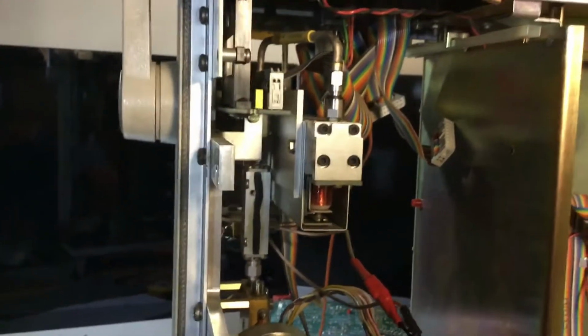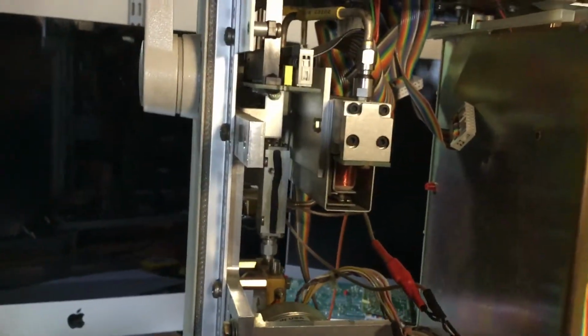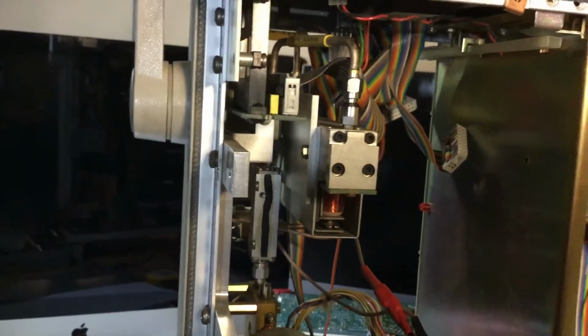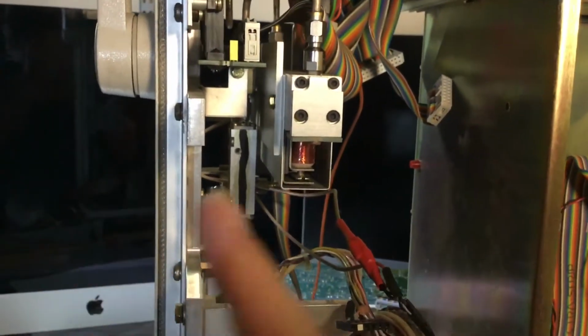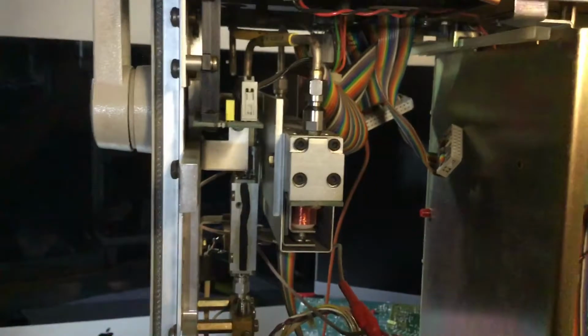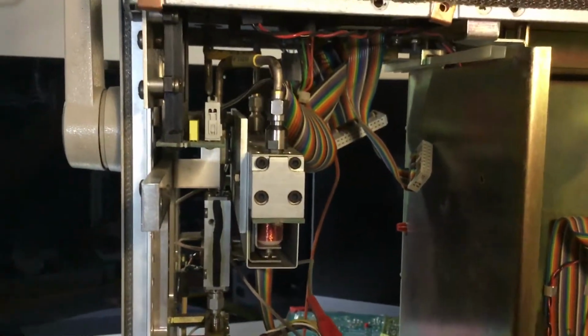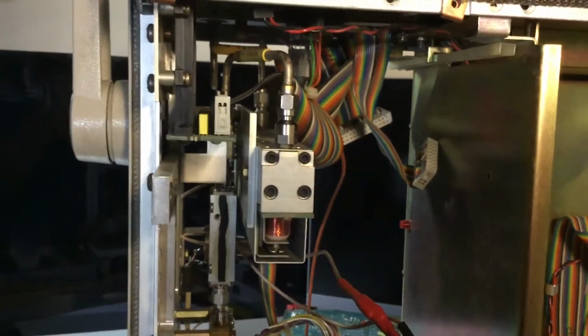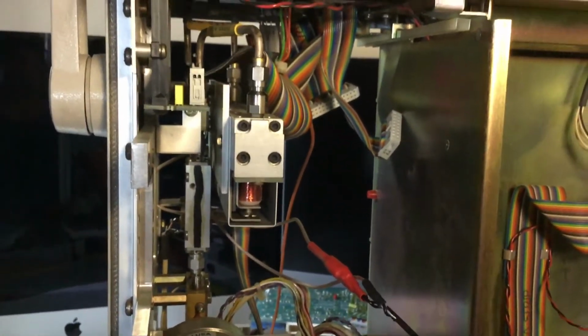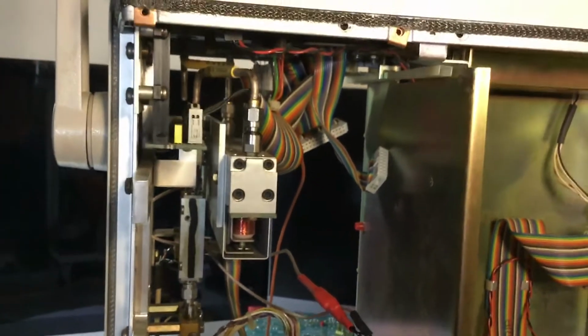Now there's a DAC value inside the calibrations menu within the test set, which sets the voltage that's given over the entire frequency range. So we've got a 10 to 20 GHz frequency range, and as per the calibration of the power sensors that I spoke about earlier, that'll self-calibrate, and the microprocessor will then adjust the DC voltage levels to the pin diode attenuator here to match the level that it should be giving out in power. So it reads its own power level and then stores that in memory and calibrates it across the entire frequency range. Now it's failing that calibration sequence on this particular test set.